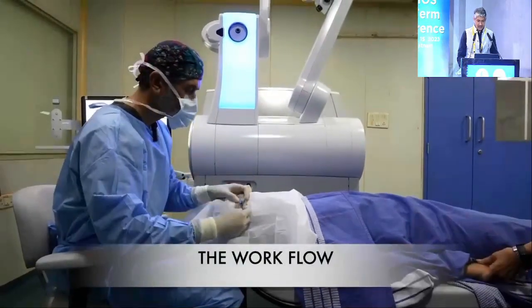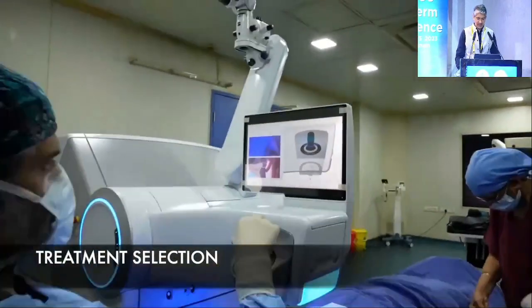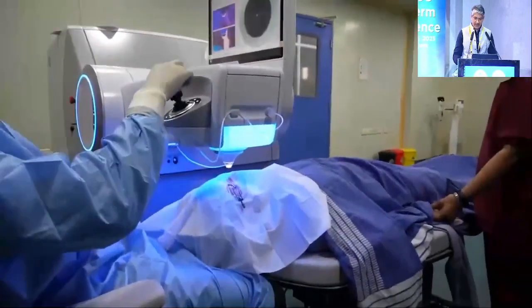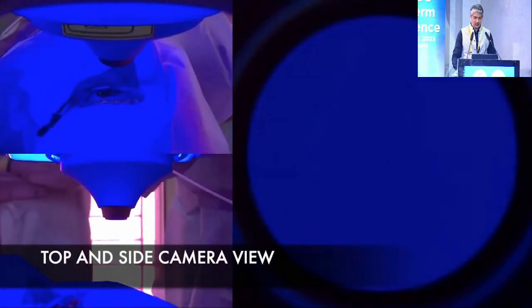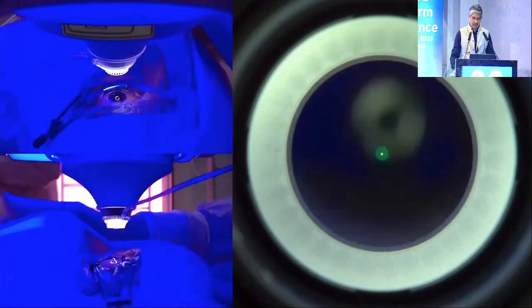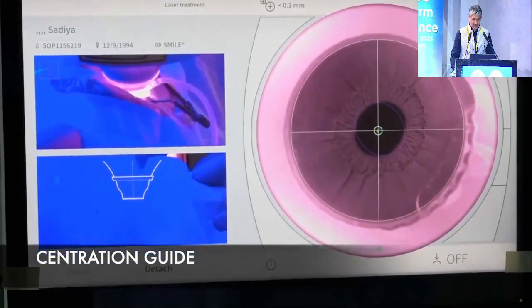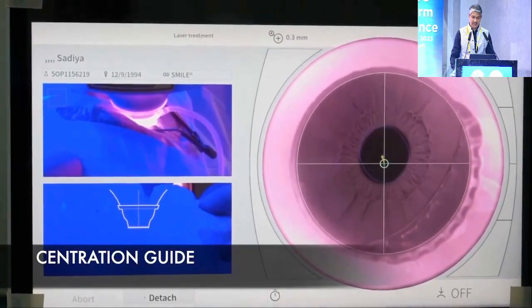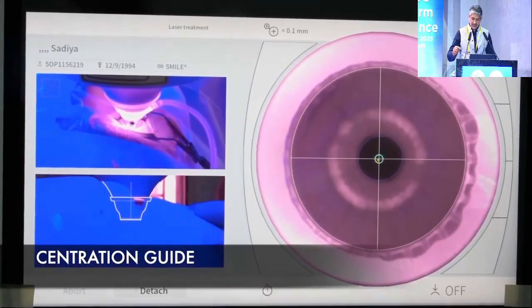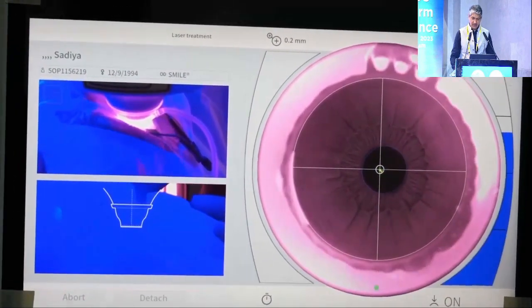If you look at the workflow of the VisuMax 800 and how it differs from the 500: you have a laser arm that descends, you select the treatment, then you attach the PI. Instead of the bed moving up like the 500, the laser arm moves. It also has a top and side camera view so you can adjust the PI onto the patient's cornea by looking at the cameras, and then there is infrared for the centration guide.